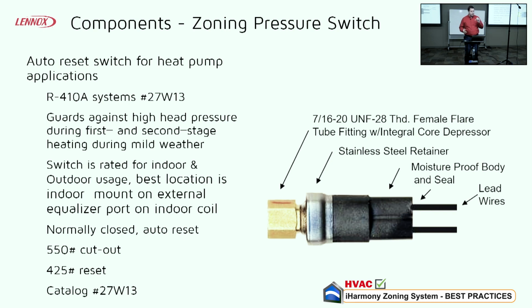So what this pressure switch is meant to do, it wires straight back to the zone board. And it cuts out, you'll notice here, at 550. So the idea is, if there's a scenario where you're running full tilt on a variable capacity unit in heat pump mode, all your zones are open, running at 100% capacity, and now maybe 1 or 2 of those zones satisfy, the airflow reduces on your indoor coil, and that brings your liquid pressure up on your outdoor unit. The zone system doesn't automatically stage down the compressor when those zones satisfy.